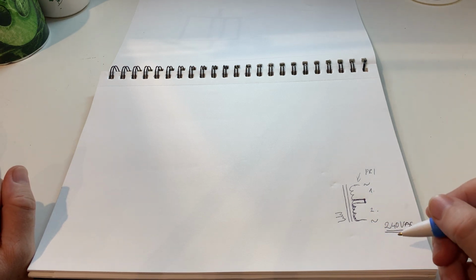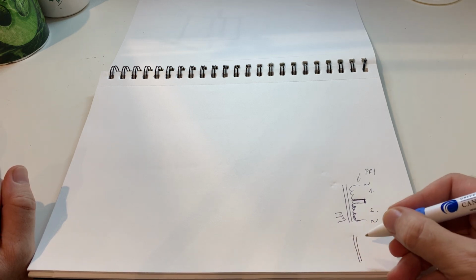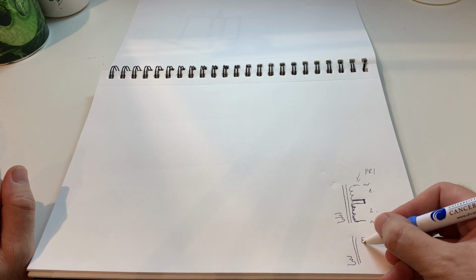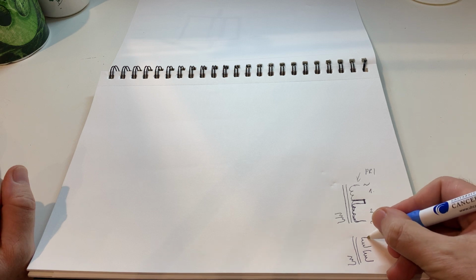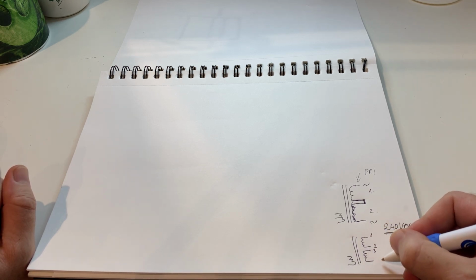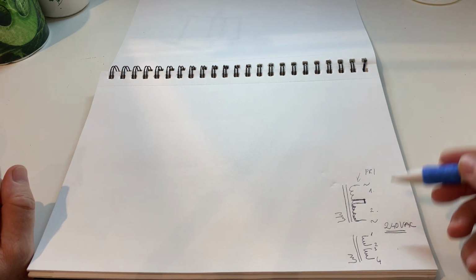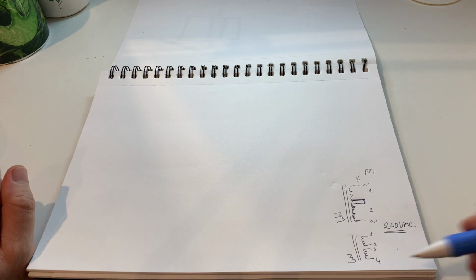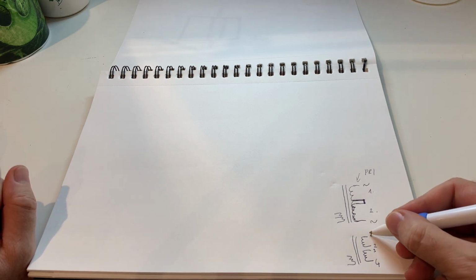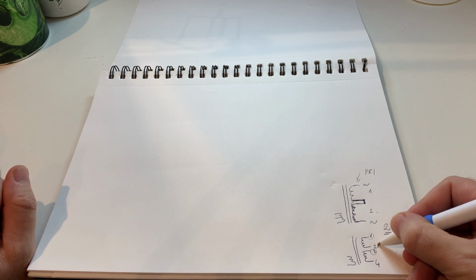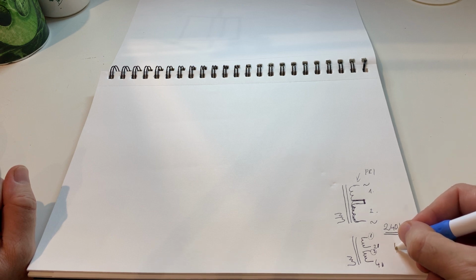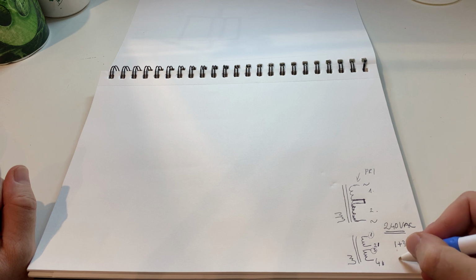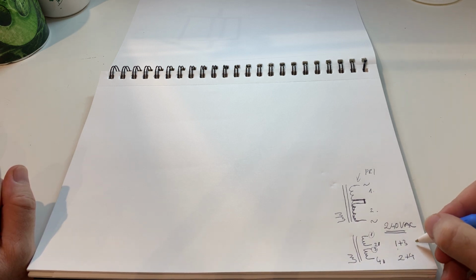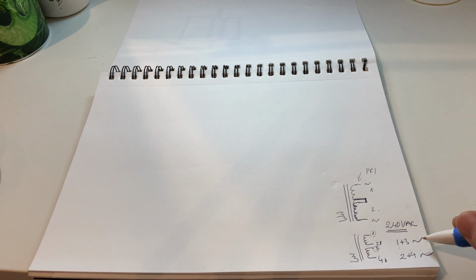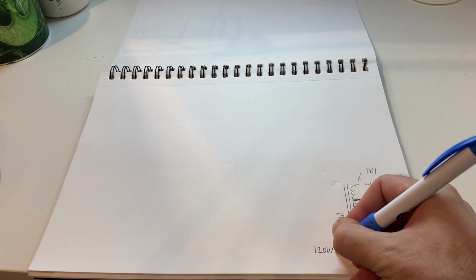And if you have 120, this is how we connect it. It's the same transformer, same secondary, one winding and a second winding. Let's call them 1, 2, 3, 4. In the first case we connected 2 to 3 together and the input was from 1 and 4. But for 120 volts, we connect number 1 with number 3, and number 2 with number 4, then these connect to your line voltage, the neutral and the hot. This is for 120 volts operation.